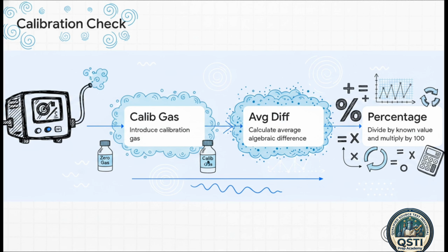First, you introduce zero gas, which is basically perfectly clean air with almost zero VOCs, just to baseline the machine. Then, you introduce your known calibration gas. You do this whole cycle 3 times, calculate the average algebraic difference, and then figure out the percentage of variance. Think of it as a rigorous stress test for the sensors.